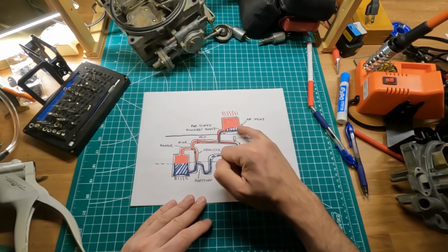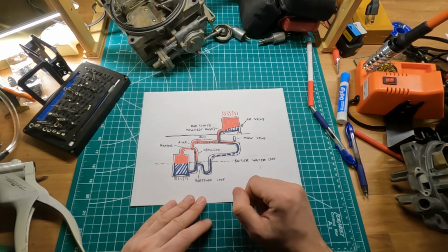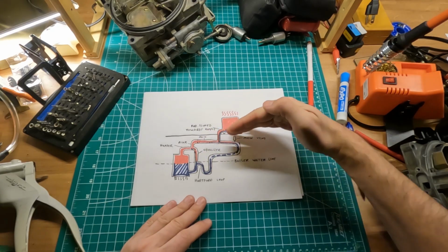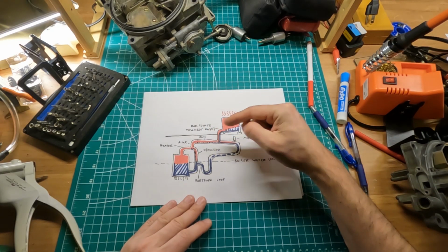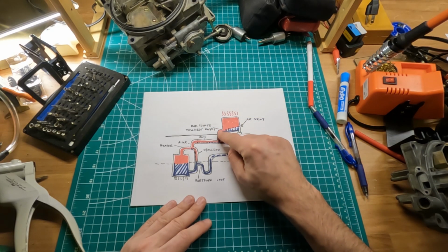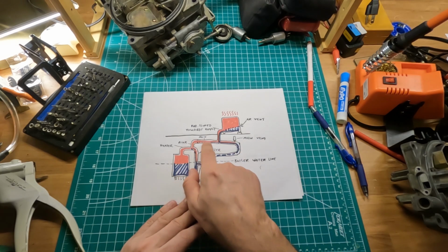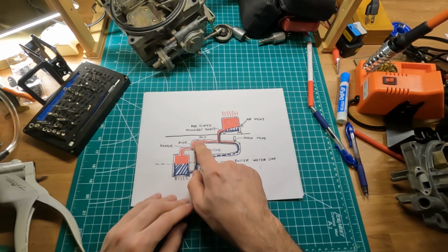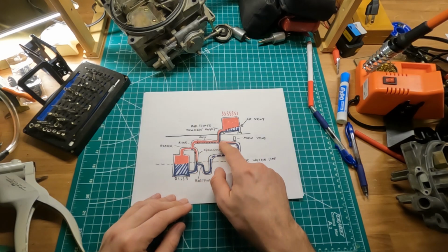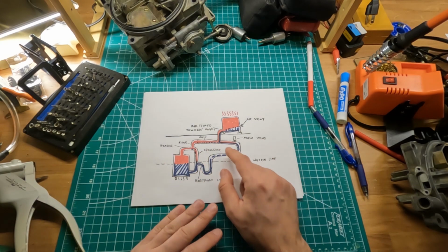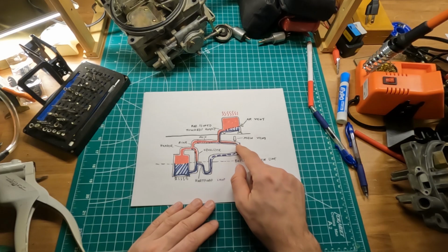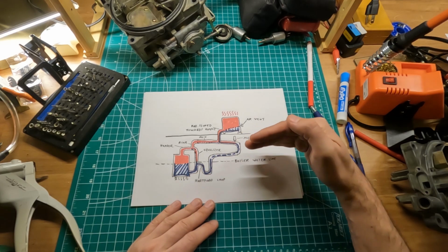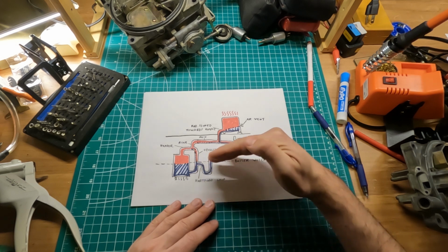condenses, so the condensate can flow back into the pipe. If you notice, this radiator is pitched in this direction, so that the condensate can return via gravity into our main pipe. And this pipe, if you notice, is pitched in this direction, so that again via gravity the condensate, in essence being water, can return back to the boiler, and then returns back via this pipe that's actually pitched this way.